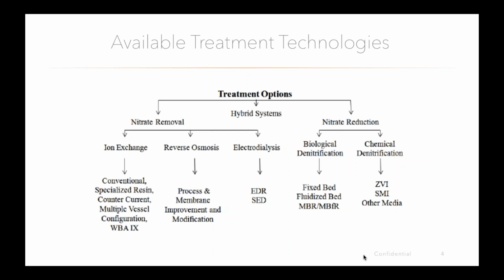So nitrate reduction technologies, what a biological process does is the organisms take a carbon source or an electron donor, typically in the form of, on the drinking water side, acetic acid. They take that and nitrate, and they convert that nitrate, they kind of digest it and consume it, into nitrogen gas and water. And so the biological process actually has the unique capability of reducing or destroying nitrate rather than concentrating it and passing it down and onto the next person.